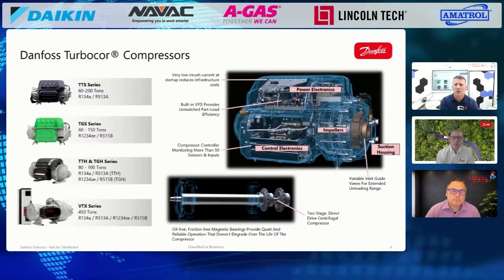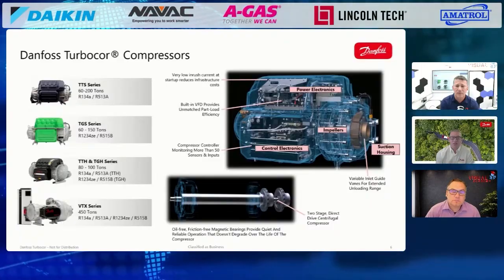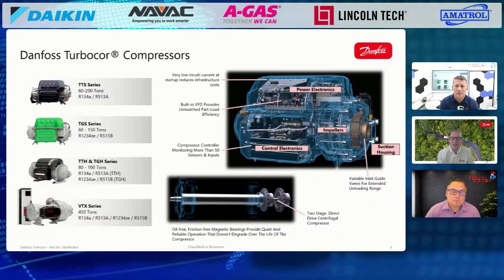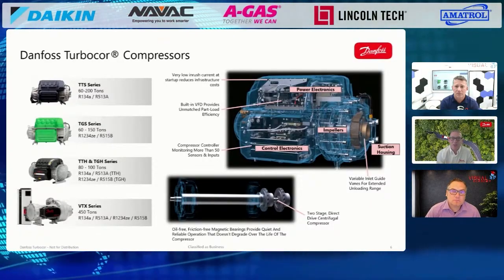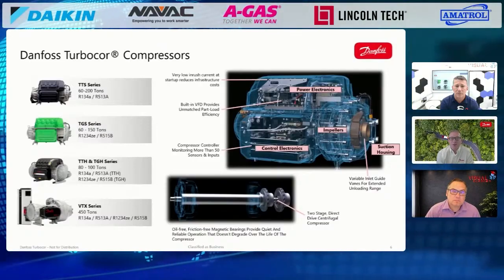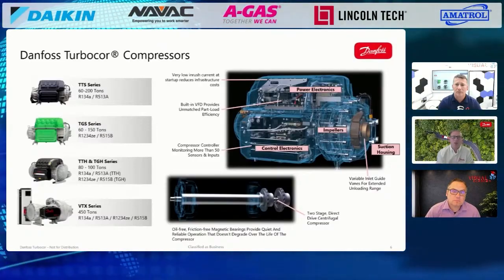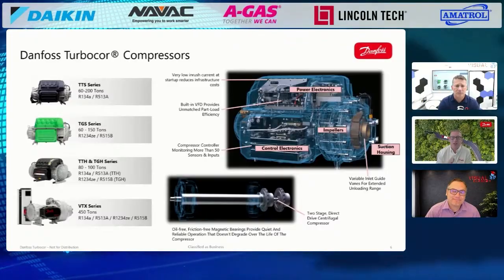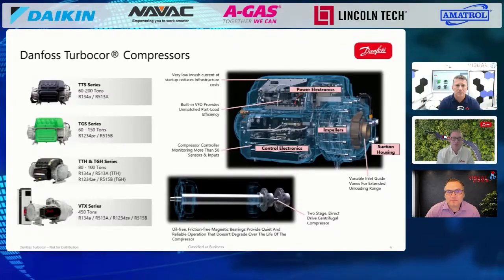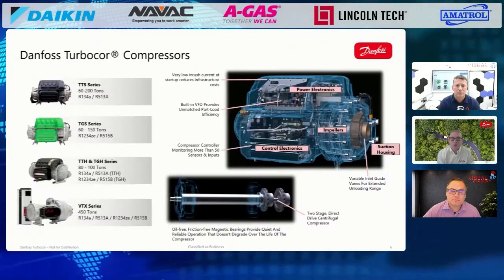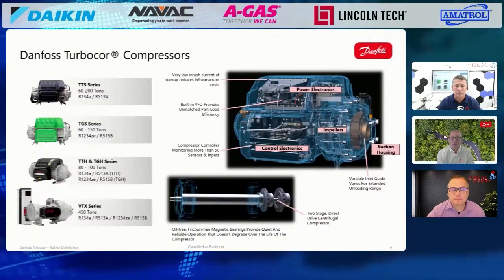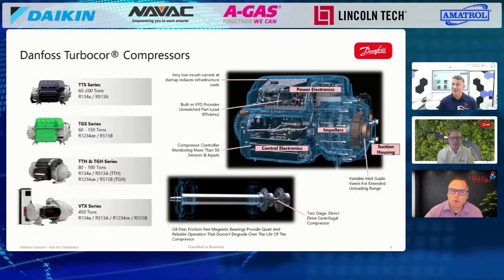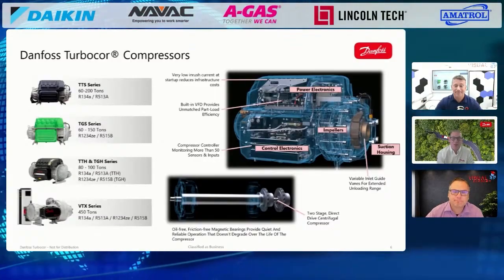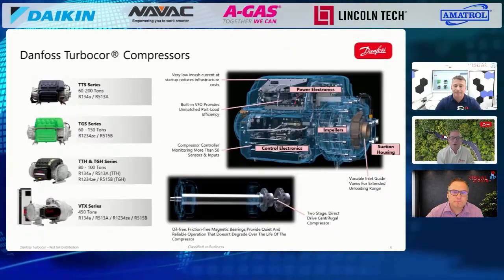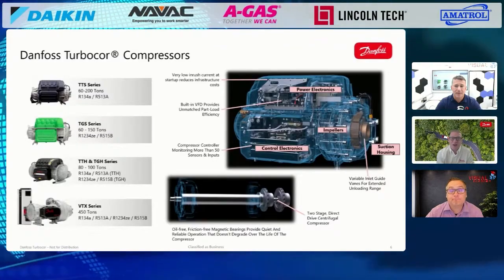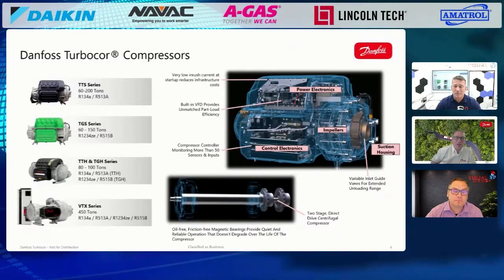In the initial days we were out there promoting swapping out any compressor and putting in a Turbocor. Now what we like to support is oil-free for oil-free, because one of the challenges is that if you have a chiller out in the field with a traditional oiled compressor, it's hard to get all of the oil completely out of that system. So if you put a Turbocor in there, the oil is going to cause issues—that's one thing to be aware of.